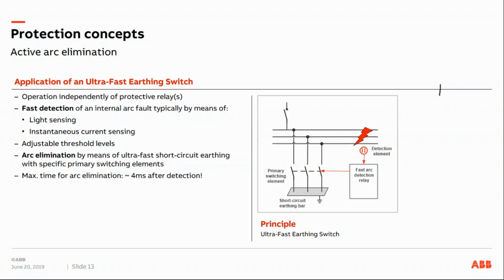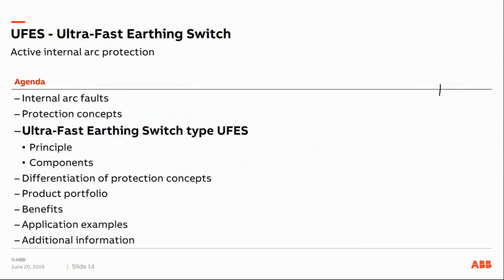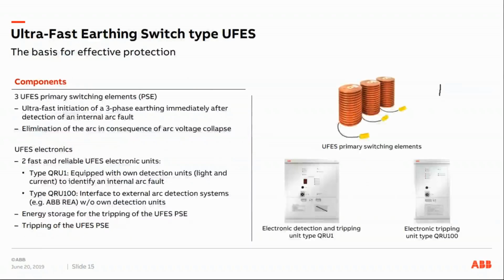Switching open again. So let's have a closer look at the UFES, its principle and its components. The UFES consists of three primary switching elements, which you can see here in a reddish orange color on the right hand side. Those are responsible for the ultra-fast initiation of a three-phase earthing immediately after detection of an internal arc fault, and the elimination of the arc in consequence of the arc voltage collapse. The tripping signal for the primary switching elements is given by the control units.